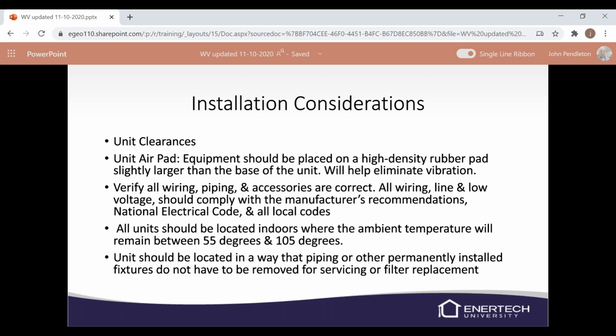A few last installation considerations that I want to rehash, I guess. Unit clearance. We've got to have a little bit of distance between the wall and the back of the unit, and we've got to be able to get to the refrigerant components. So I would say 2 foot around the entire unit. And make sure it's sitting on a rubber pad slightly larger than the base of the unit. It's going to help eliminate any vibrations that could be transmitted into the flooring.